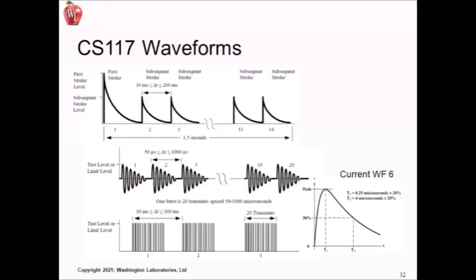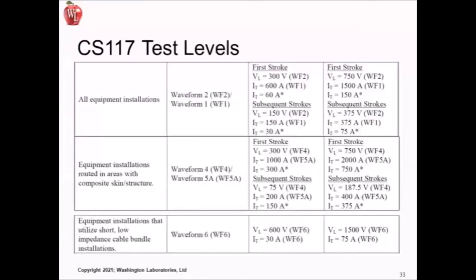Here are some of the waveforms that are specified by CS117. Again, these simulate lightning injections. So depending on the attachment point, you may have a simple transient, exponential, double exponential, or depending on where you're injecting, you may end up simulating a damped oscillatory type of waveform. So there's quite a few waveforms, and one that is similar to perhaps an EFT type of test, which is the one waveform on the bottom. Here's some of the test levels, the different waveforms. And you can see that some of them depend on, these are aircraft basically requirements. So depending on where the equipment is installed in the aircraft, you'll have different waveforms.